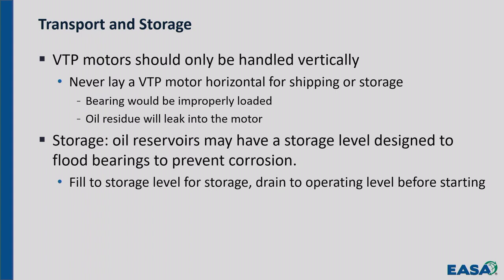If this is for storage versus operation, not all the technicians at the customer's facilities are aware of that, and they just fill it up to the highest level marked on the sight glass without seeing that it says storage level or anything like that, and they run the motor and they've got all kinds of oil leak issues. Okay.